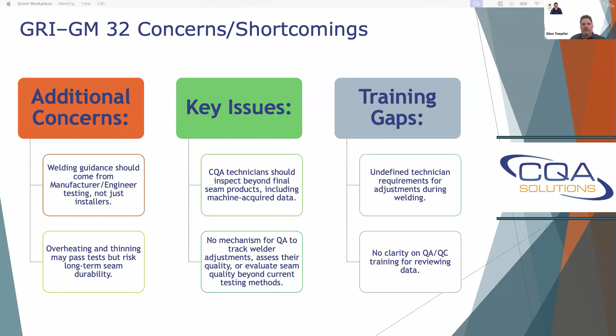peel and shear test. Other key issues with this: technicians should inspect, it's not recommended, but they need to inspect the machines, the setup of the machines, all the data being acquired. And then there is no mechanism for the QA to track the adjustments and actually assess their quality. We can see that they changed something, but what do you do there? There's no guidance on what to do. Then there are gaps too, because there is no training for the technician that's doing the welding and what changes they can make. No clarity for reviewing the data and what is a problem.